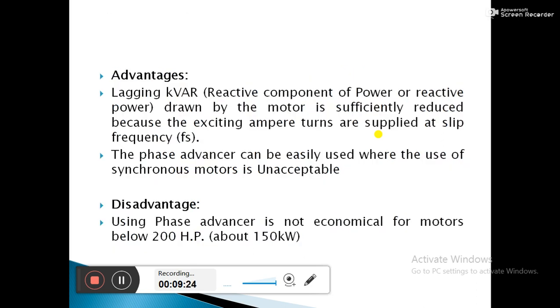The advantage of the phase advancer is that the lagging reactive power drawn by the motor is sufficiently reduced because the exciting ampere-turns are supplied at slip frequency. The phase advancer can be easily used where the use of synchronous motors is unacceptable. The main disadvantage is that using a phase advancer is not economical for motors below 200 HP; it is only suitable for motors above 200 HP.